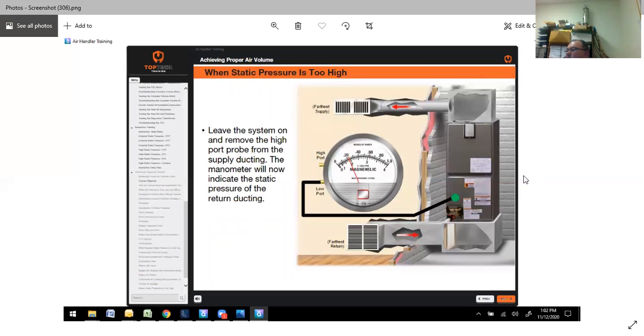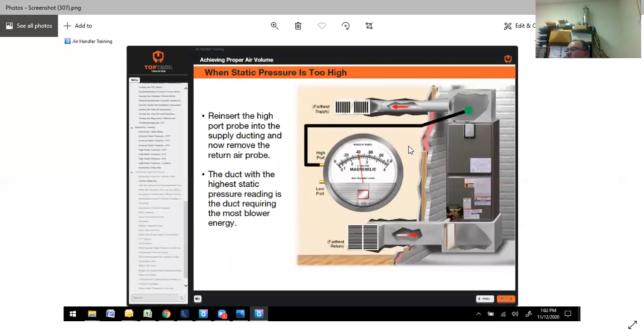Not the end of the world. That's pretty decent. So that's on our return side. Now we'll change that around. So now we'll put the supply probe back in, pull this one out. Now we see where our high static is, 0.4. So we know we've got some issues on our supply side. That's what's causing the energy consumption, the noise, comfort issues.